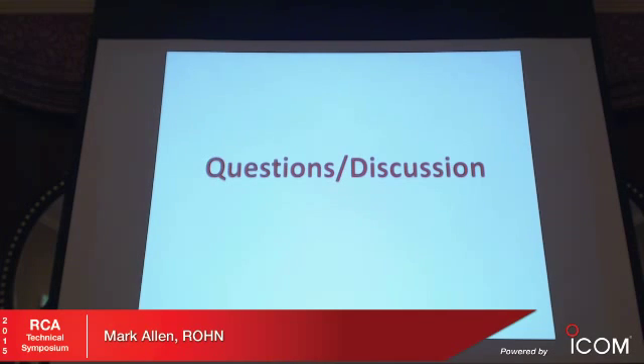Is your monitoring data SNMP compliant, so that you could bring the monitoring information back into a network manager of managers, or is it a dedicated system? Yes, it is. Absolutely. We can generate SNMP traps. This local PC that's installed at the base of the tower communicates using a publish-subscribe protocol up to the cloud server, which you saw in the network diagram there.